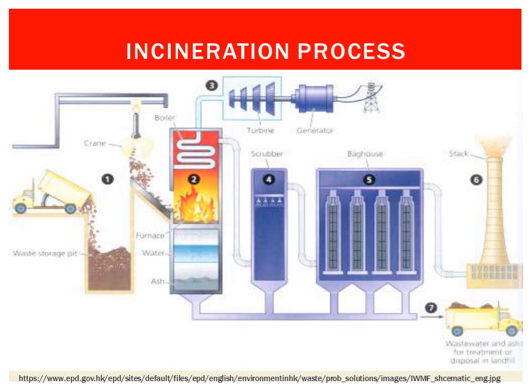The second component is the boiler, where the energy content of the hot off-gases is utilized for steam and electricity generation. The third component is the system for removal of residues — these are 20 to 40% of the initial waste and are collected and transferred to specific systems for further cooling. The fourth component is the removal of suspended particles and gaseous pollutants. These gaseous pollutants may include carbon monoxide, carbon dioxide, nitrogen oxides, and sulfur oxides.